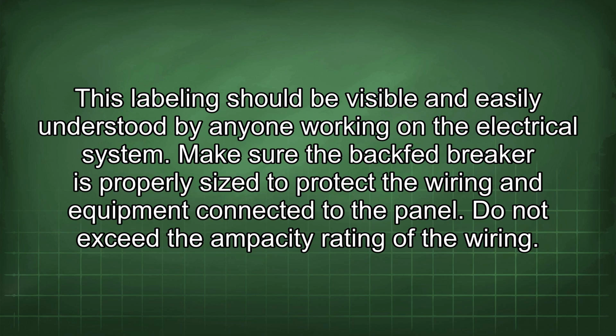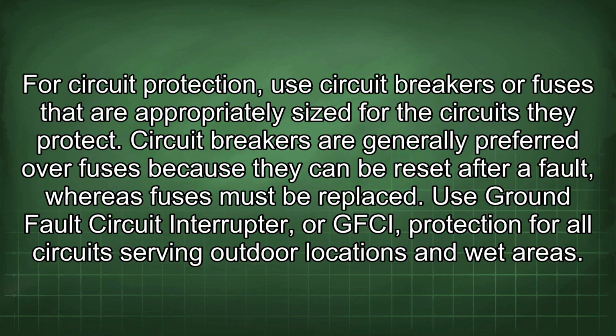Make sure the backfeed breaker is properly sized to protect the wiring and equipment connected to the panel. Do not exceed the ampacity rating of the wiring. For circuit protection, use circuit breakers or fuses that are appropriately sized for the circuits they protect. Circuit breakers are generally preferred over fuses because they can be reset after a fault, whereas fuses must be replaced.